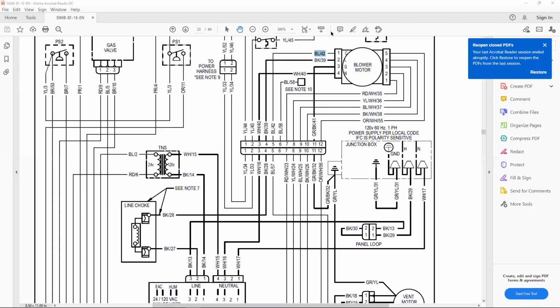I didn't know why it was doing that, I kind of was thinking it was my meter, but then I'd stick it on my meter and on the one, it would stay at 4.6 and not bounce around. So I was confused. So that could actually be an indication of a bad connection, if you're seeing that bounce around on one lead versus not the other. So I've got that ECM motor right here. So this is a 3-phase motor. So I can throw my leads in here. And like you said, I should get equal resistance across all of these. So it should be fairly stable, assuming I get the leads on there right.